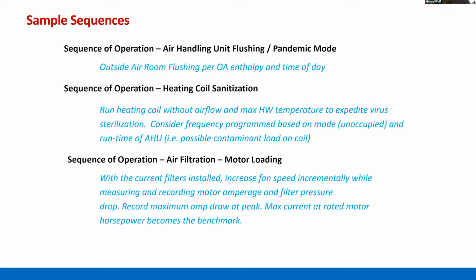And then with the occupancy sensors now, we still are able to implement those static pressure resets. Some of those energy saving methodologies and sequences can stay in place because it's a little bit more controlling the building based on the occupancy and trying to find that balance between safety and energy use.